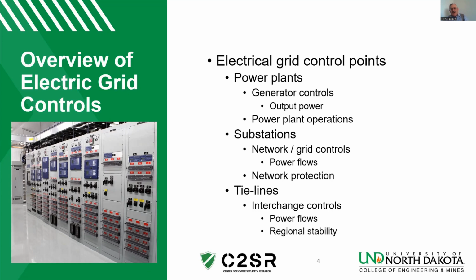So one of the things that can occur is anytime that you have a change in loading or a disturbance that takes place, resources are temporarily lost, then generation has to reroute power to the load. And if that is not successful for a moment in time, energy can be built up in the generator rotating masses. And once power is able to go back to the load, we have the problem of that excess energy stored in the rotating masses and also seen as changes in frequency. And so as the system over matters of seconds to maybe 30 seconds, the system will begin to swing in generator output, and the amount of power that is shared between the generators.